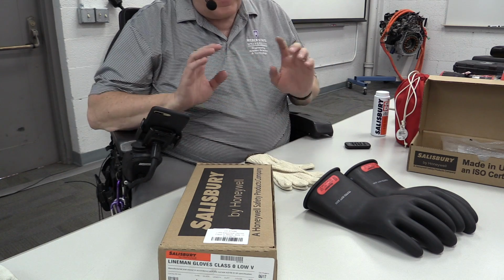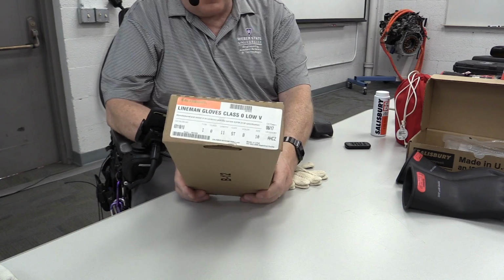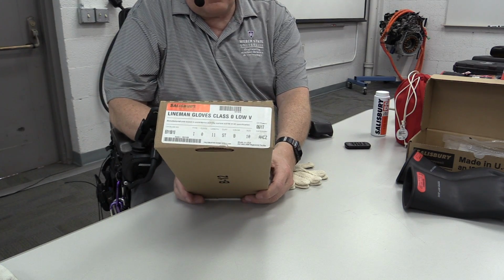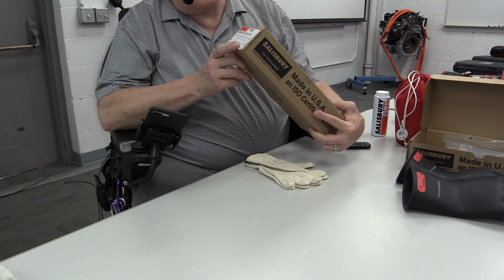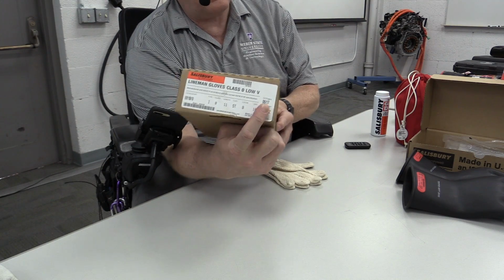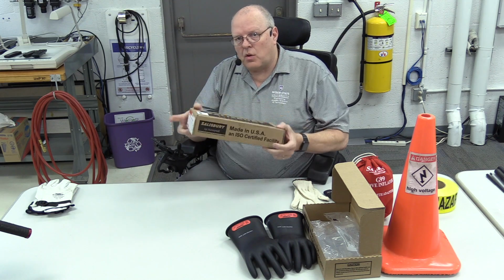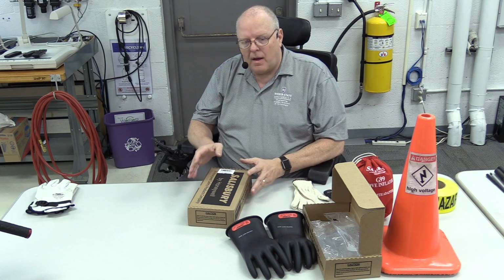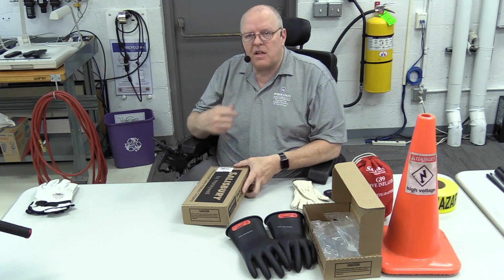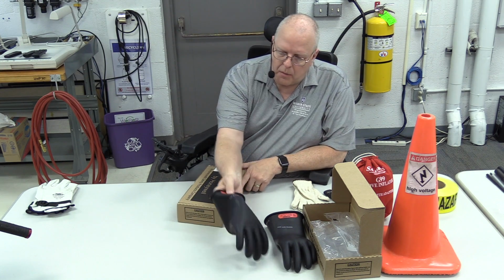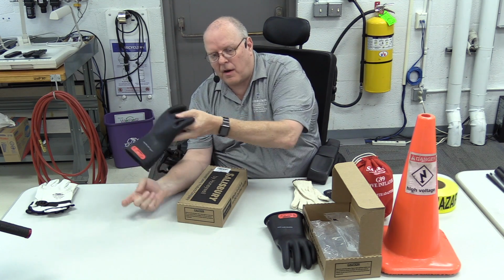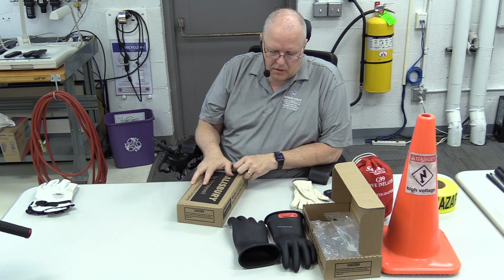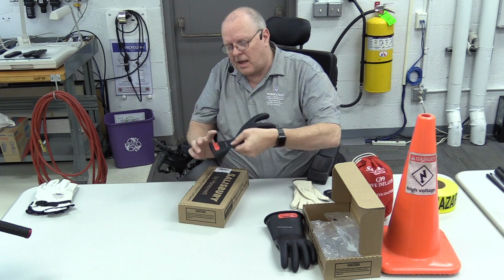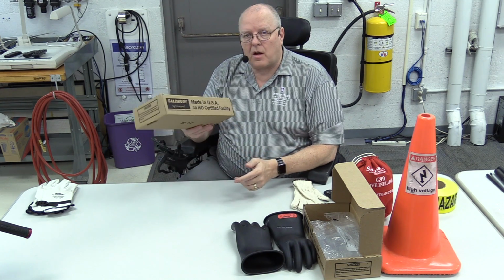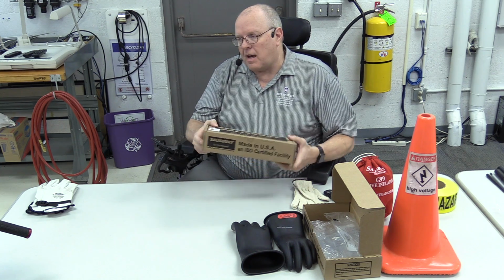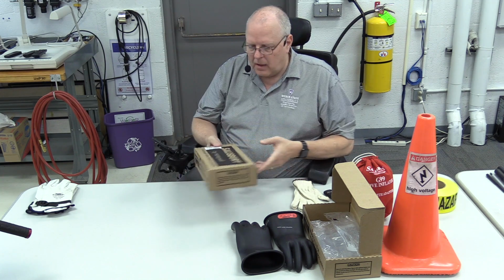Quick review on the glove expiration date. This box I just got yesterday in the mail has a date of June 2017. As soon as I open these, I have 6 months before I either need to buy a new pair or send these out to be recertified. Don't get caught up on the 'tested on' date. When we started teaching these classes 10 years ago, we thought you only had 6 months from the date on the glove, but that's not the case — it's 6 months from the time you open them, as long as the date on the box is not more than a year old. I know that's confusing.